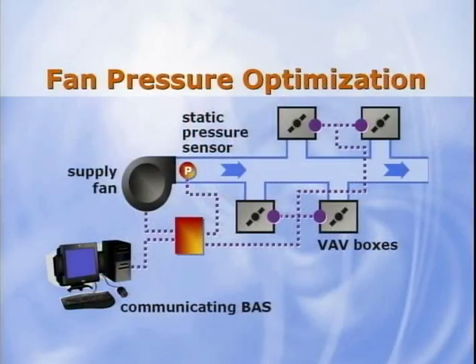Each VAV box controller knows the current position of its air modulation damper. The BAS can continually poll these individual box controllers, looking for the one with the most open damper. The fan static pressure set point can be reset lower. The VAV box, in turn, will be nearly wide open in order to maintain the airflow necessary to cool the space. The result is that the supply fan generates only enough static pressure to push the required quantity of air through this critical VAV box.